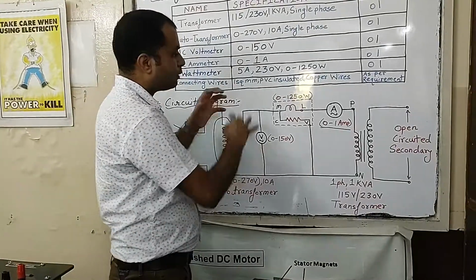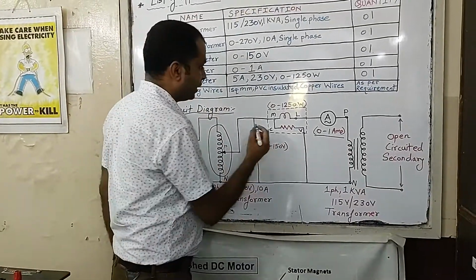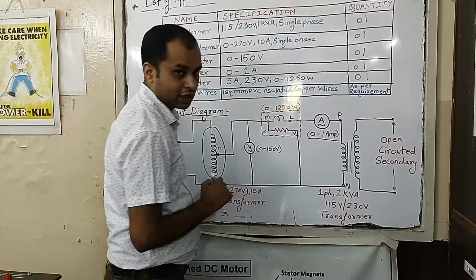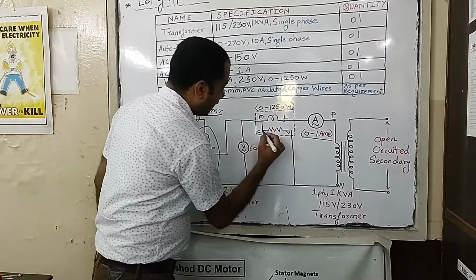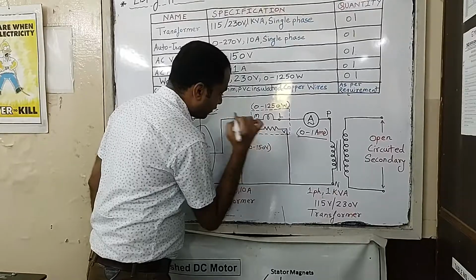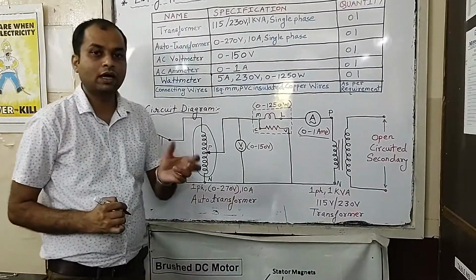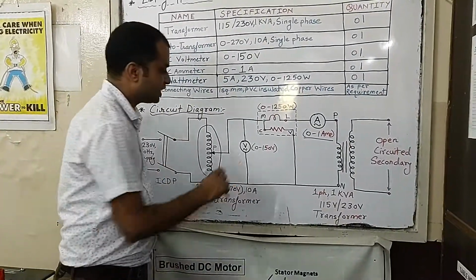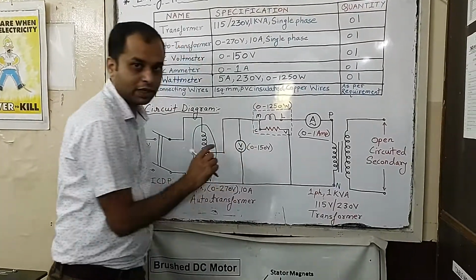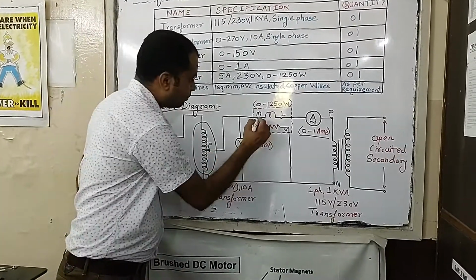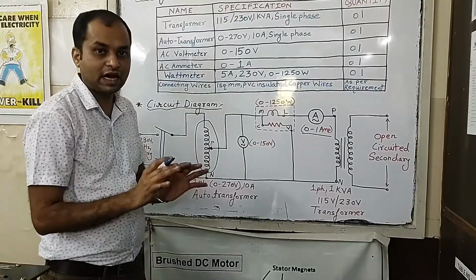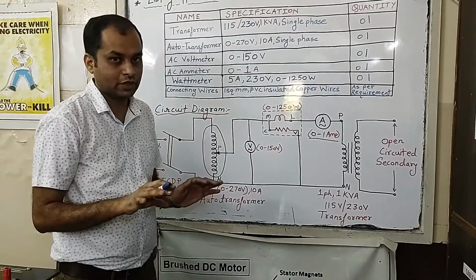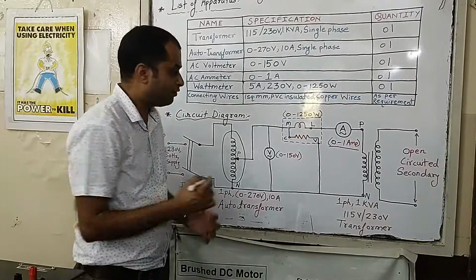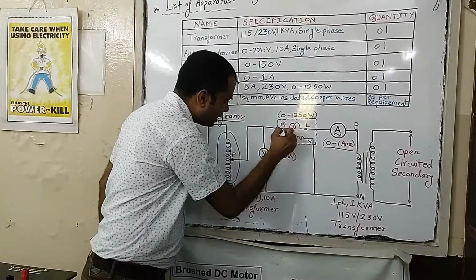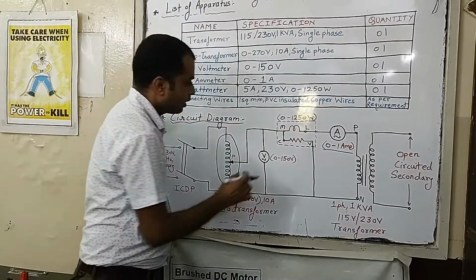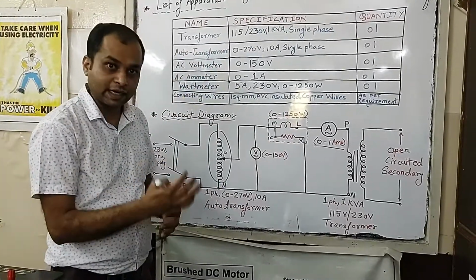Now we have to complete the connection of the wattmeter that we are looking at here. As we saw while looking at the wattmeter, there are two further terminals, the C and V terminals. M and C are not internally connected, so we have to take a wire and make the connection between the M and C terminals. C and V are internally connected.